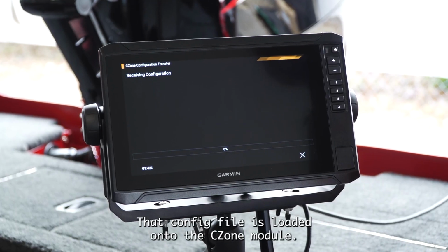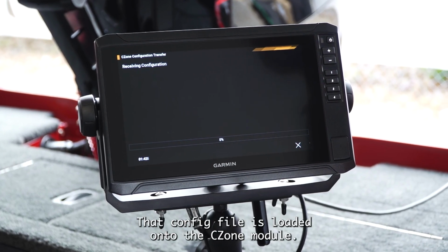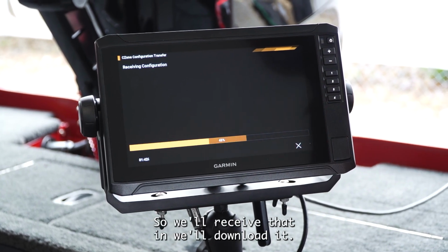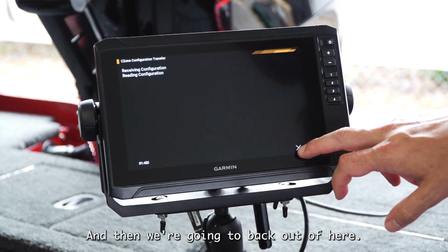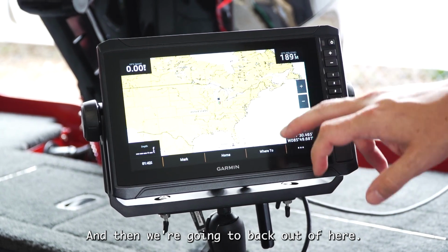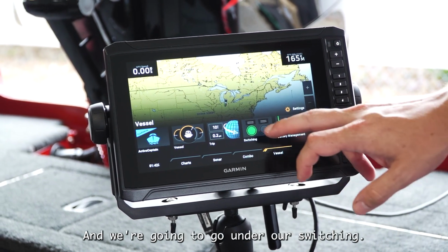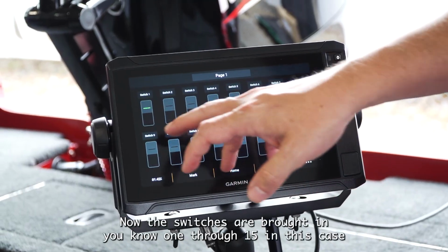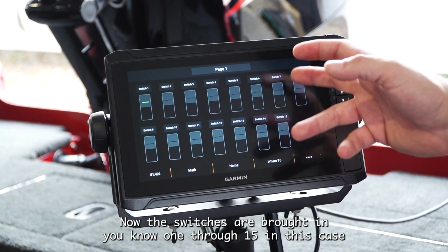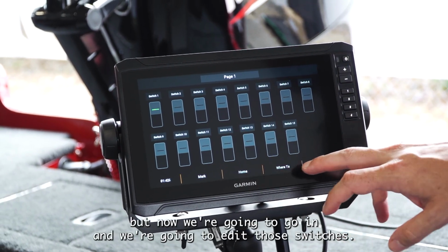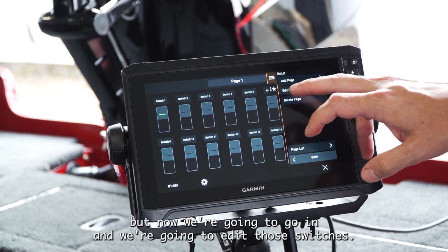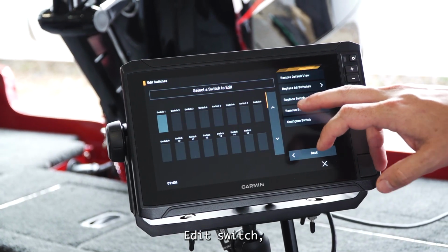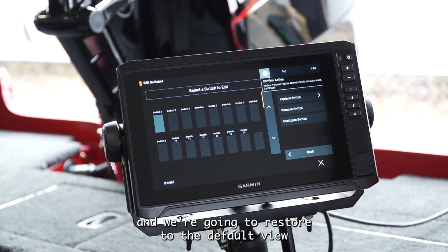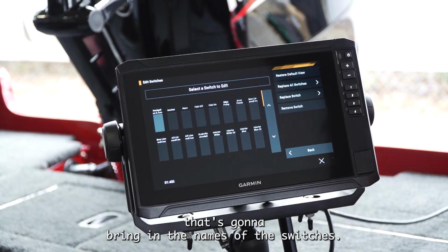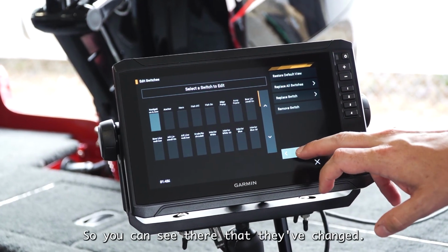That config file is loaded onto the CZone module, so we'll receive that in, we'll download it, and then we're going to back out of here and we're going to go under vessel and we're going to go under our switching. Now the switches are brought in 1 through 15 in this case, but now we're going to go in and we're going to edit those switches. We're going to edit that page, edit switch, and we're going to restore to the default view. That's going to bring in the names of the switches so you can see there that they've changed.